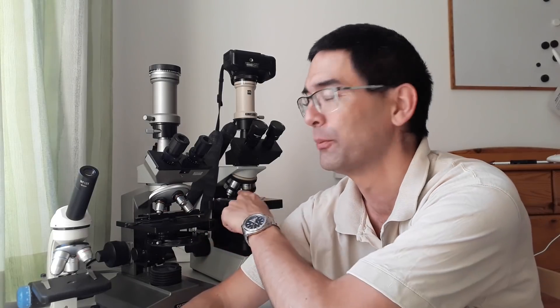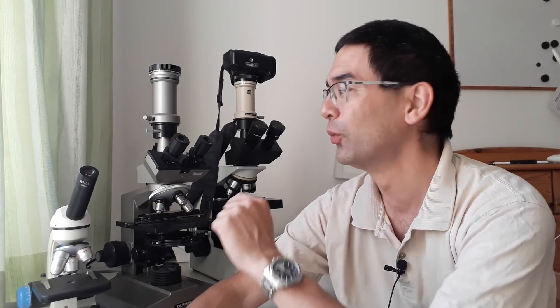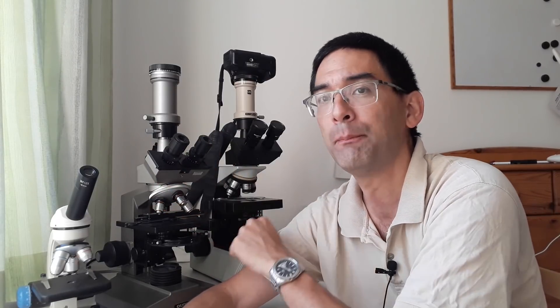There is one last thing I want to say: I wanted to buy a new objective for my CH40 microscope, and I called up the company. They told me sorry, they don't have those objectives anymore because they changed the system a long time ago. Nowadays all of those high-end companies have moved towards so-called infinity systems, and those infinity optical systems are not compatible with the traditional 160-millimeter system that those microscopes have. This is unfortunate, but because those high-end microscopes were so popular many years ago, there is still a second-hand market. This allowed me to buy different parts over eBay — for example, for this CH40 microscope I bought new phase contrast objectives and a phase contrast condenser.